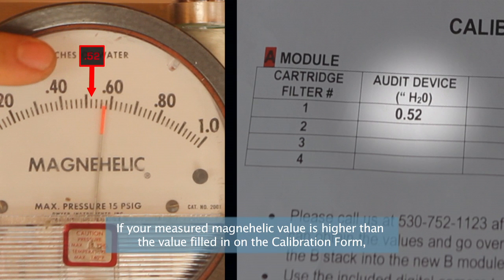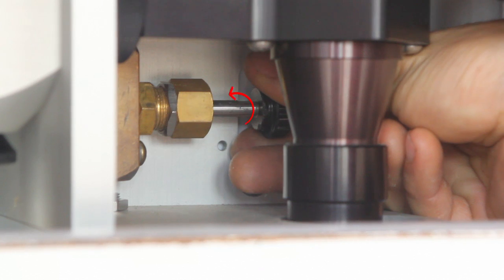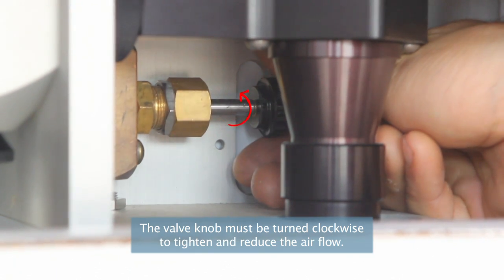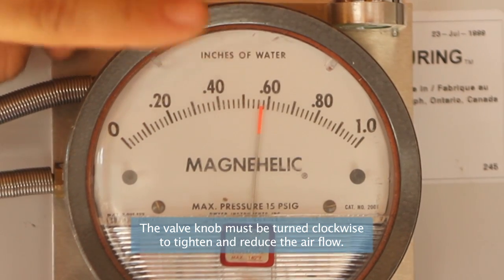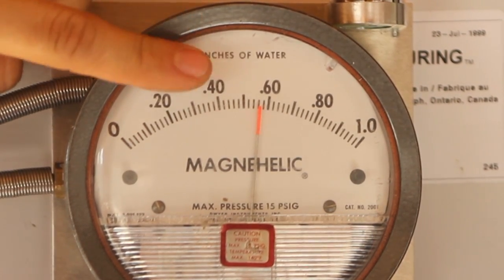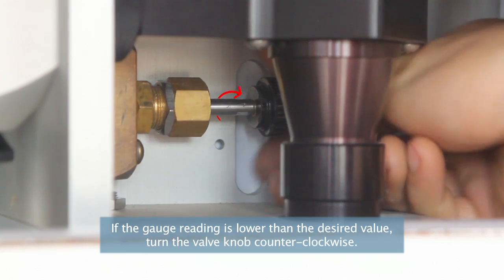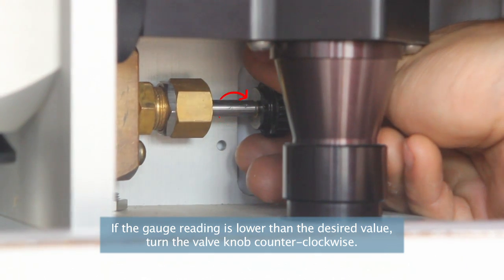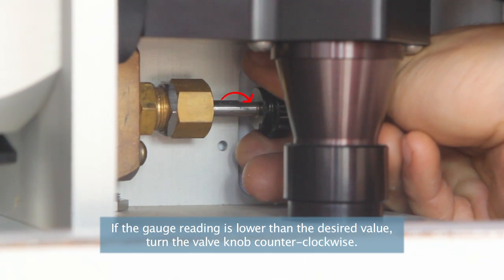If your measured magnehelic value is higher than the value filled in on the calibration form, the valve knob must be turned clockwise to tighten and reduce the airflow. If the gauge reading is lower than the desired value, turn the valve knob counterclockwise.